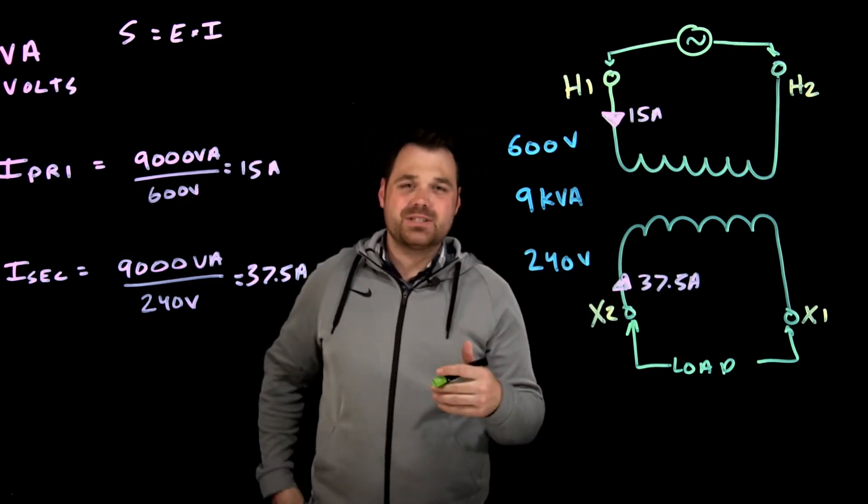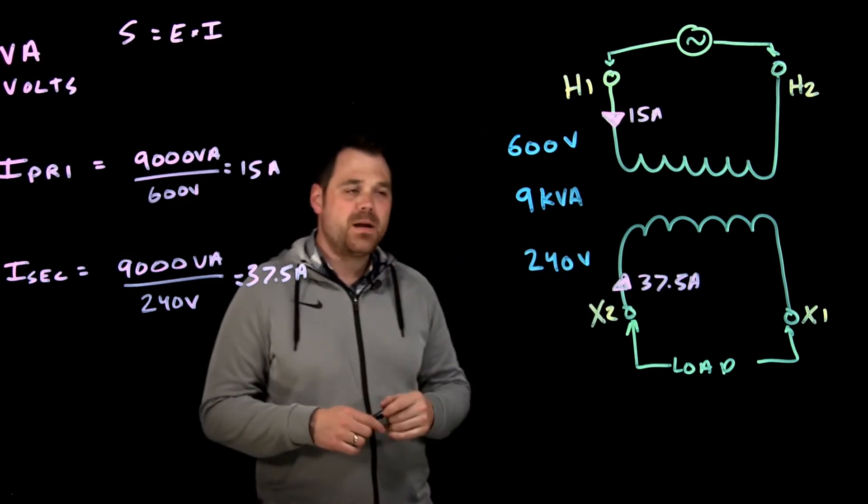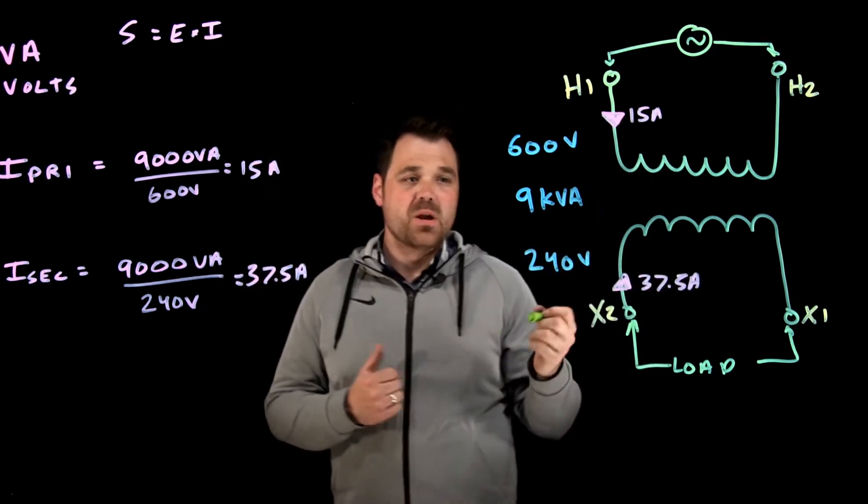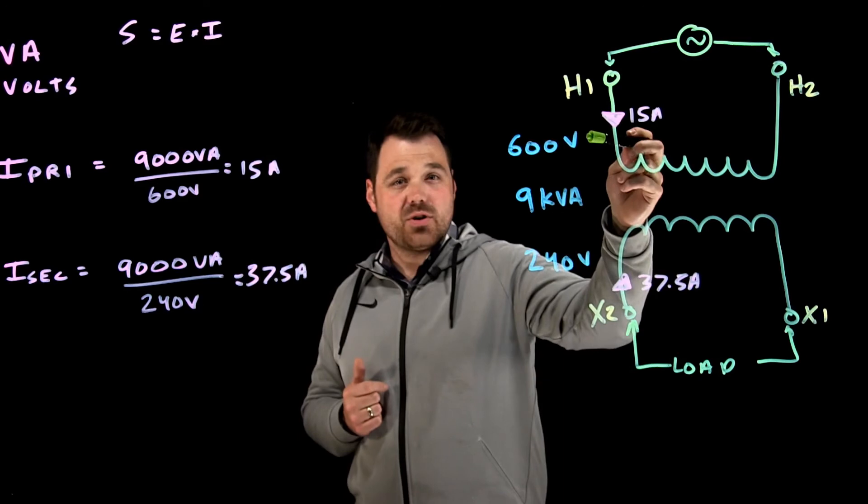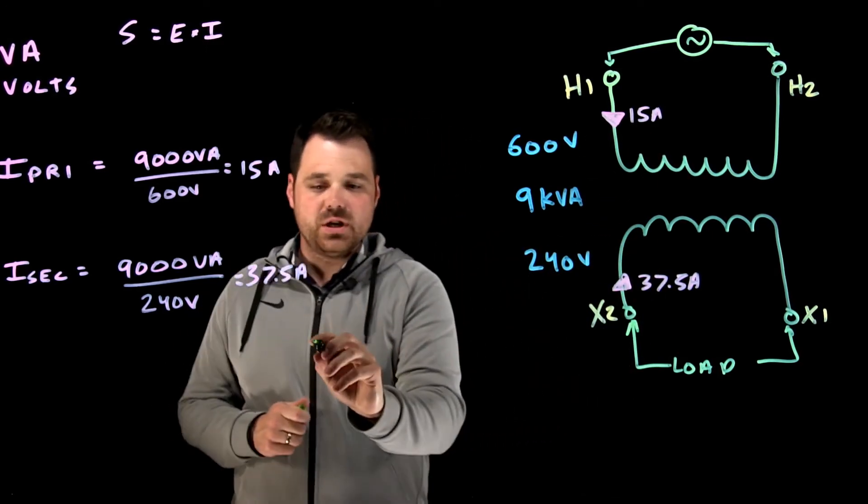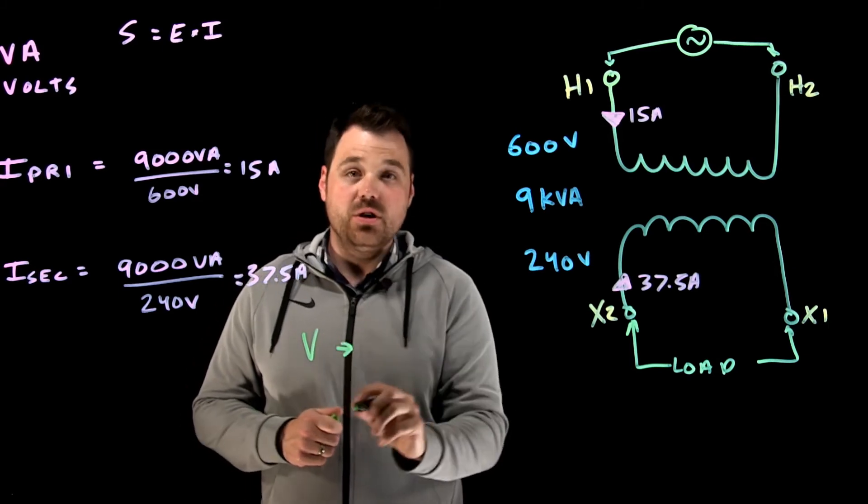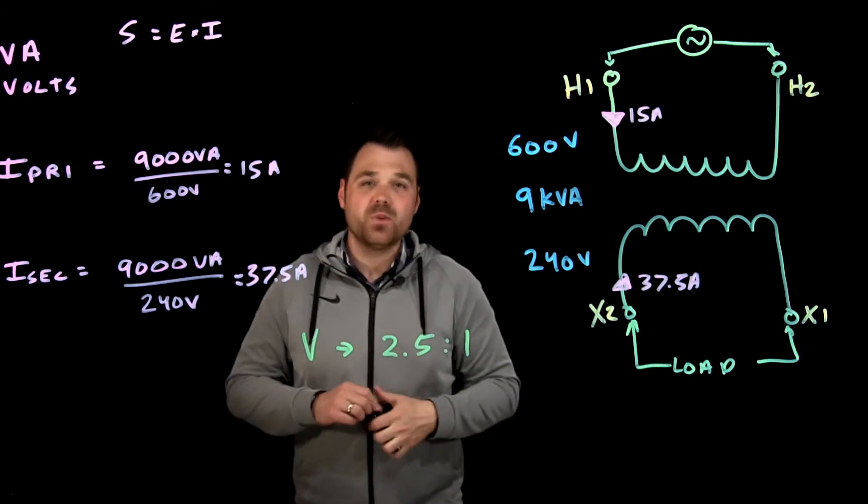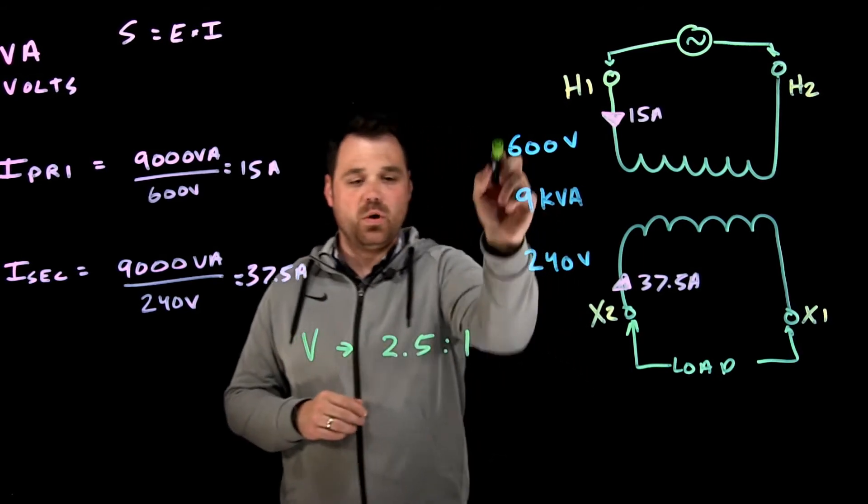The last thing I want to talk about is some of the ratios that we see here. We said we are a 600 to 240 volt transformer. If I go 600 divided by 240, that gives me my voltage ratio. So my voltage ratio here would be 2.5 to 1.